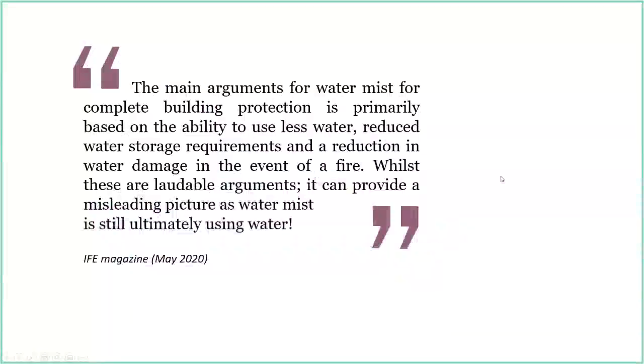I've got a quote here from International Fire Magazine, IFE Magazine, from May 2020, so it's quite recent. This speaks into this area about reducing water storage and reducing water damage. It says: whilst these are laudable arguments, it can provide a misleading picture, as water mist is still ultimately using water. So again, it's not quite as rosy as the picture is sometimes painted. What's absolutely important is performance in terms of fighting fire—surely that's the most important thing, rather than the reduction of water storage and water discharge.